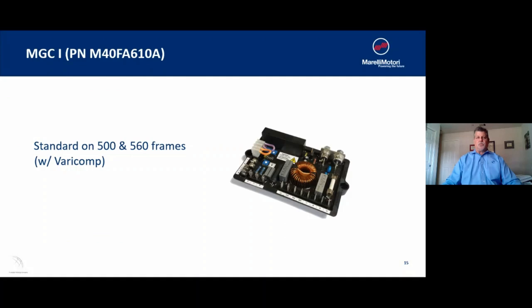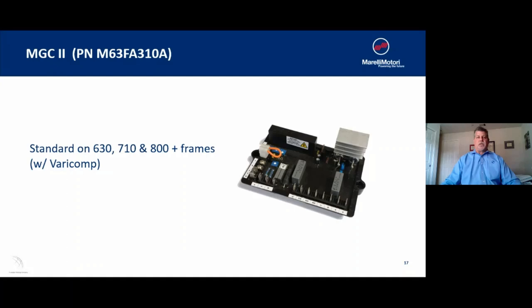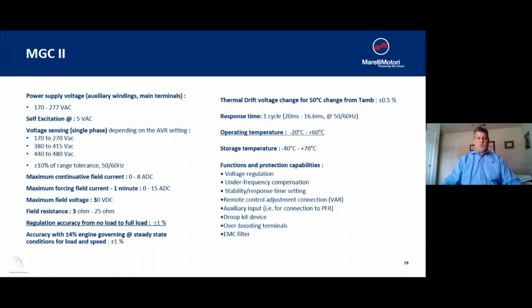Moving on to the MGC1, standard on our 500 and 560 frame, it uses the Varicomp as an option for overboost capability. It's one of our older voltage regulators, so it is plus or minus one percent accurate and the operating temperature range is only 60 degrees C. Its twin is the MGC2, standard on the 630 frame and larger, with Varicomp available for overboost to improve voltage drop on larger AC motor loads. Both the MGC1 and MGC2 provide for a remote rheostat and also allow an auxiliary input for a power factor correction device.